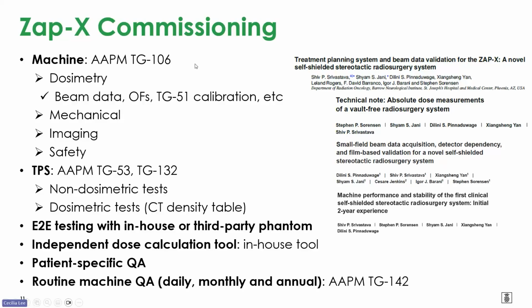There are many publications out there you can use, such as task group 106, the TPS task group report, and even the QA task group report. The very first unit was installed in Phoenix. They did a lot of early dosimetry and physics work, so you can look up their TPS commissioning publication, TG51 and TG21 calibration, data collection, and how to do output factor using different dosimeters. They also presented some machine performance over 2 years. If you're interested, you can look it up.